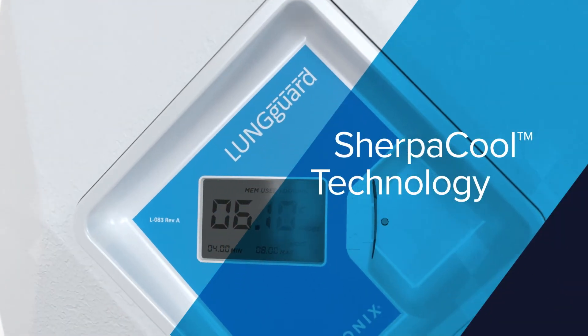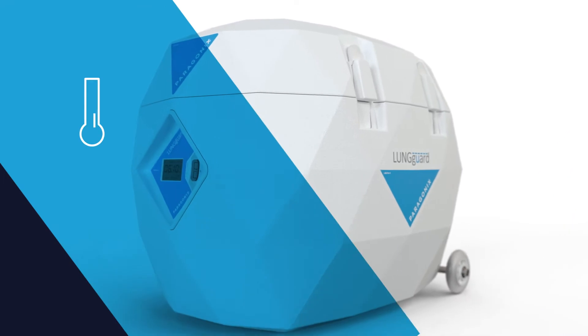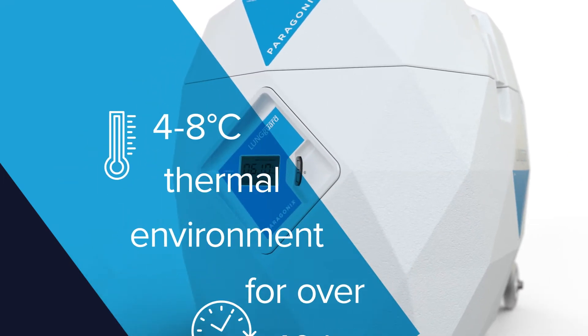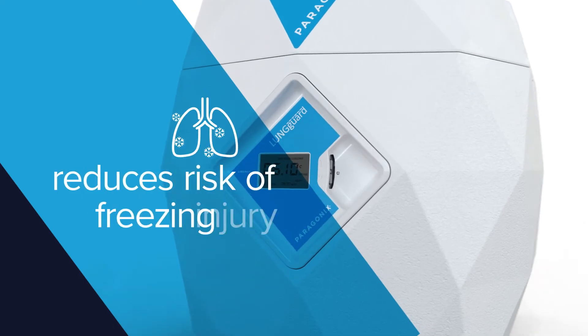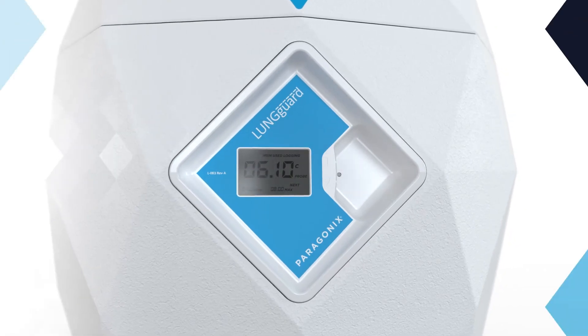Using precision SherpaCool technology, the LUNGguard has been validated to provide a consistent four to eight degrees Celsius thermal environment for over 40 hours. This reduces the risk of freezing injury to the donor organs, which is commonly associated with traditional ice storage.